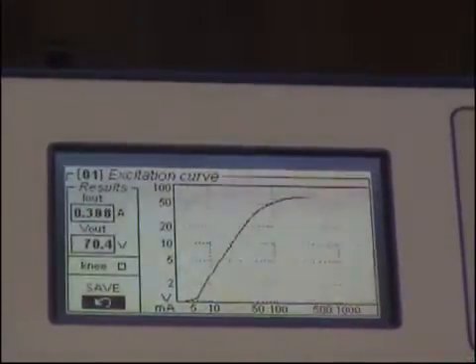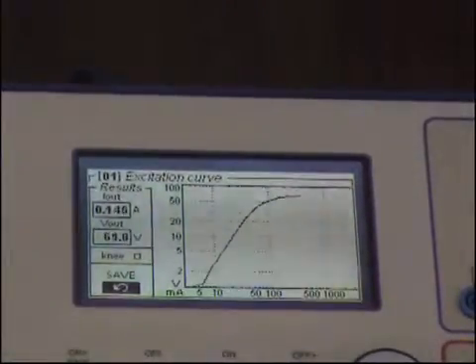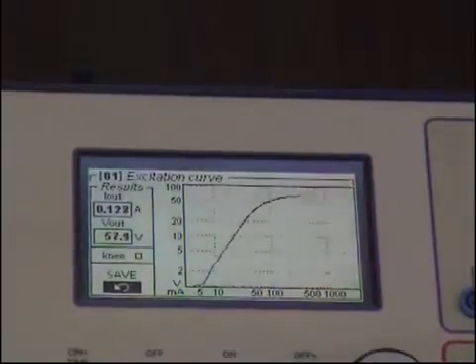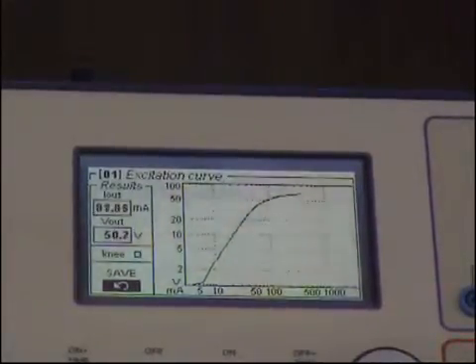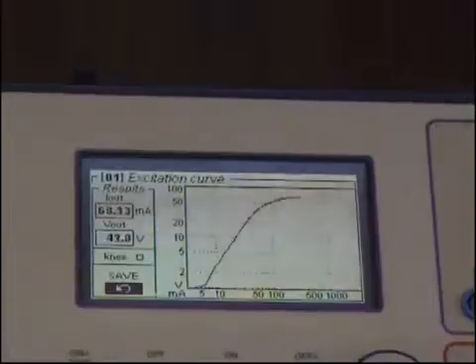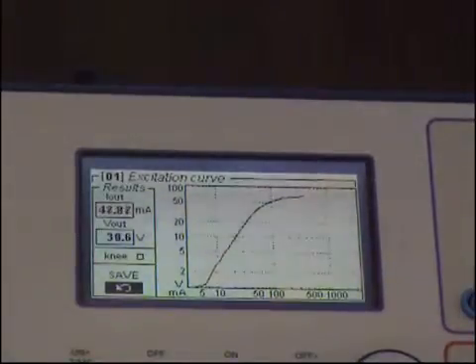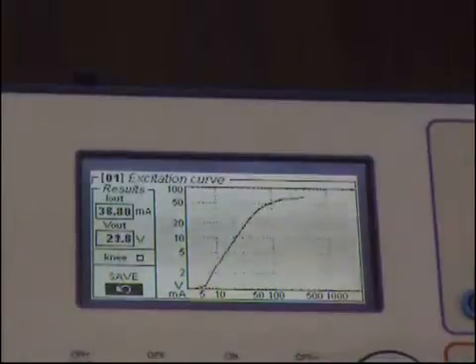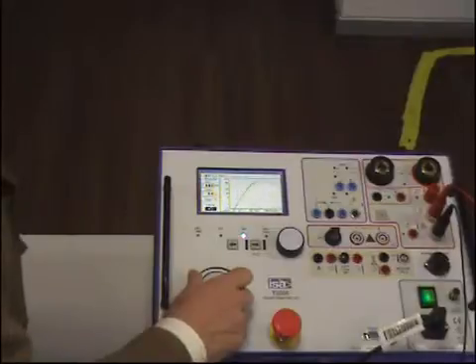Now I am beyond the knee, so I go back with the current and with the voltage. Do it slowly, because if you have saturated the transformer and don't go slowly, you leave some remnants in the core of the transformer — in the iron. This is not good because that magnetic energy you are leaving will cause trouble when the current transformer is put back into service, as that energy must be nulled before the transformer returns to normal operation.